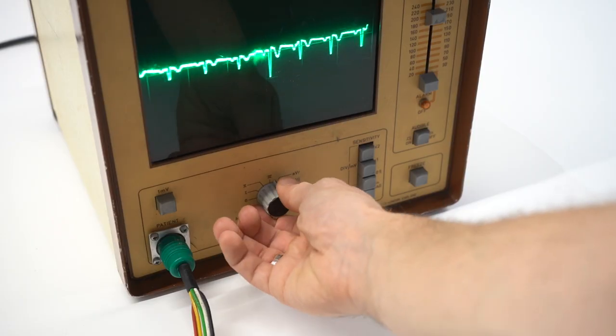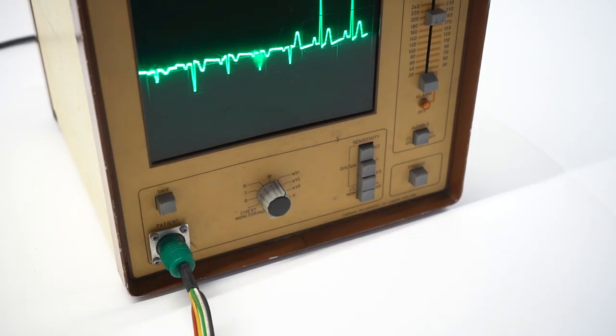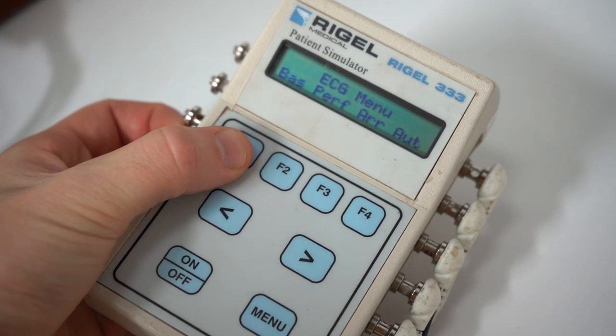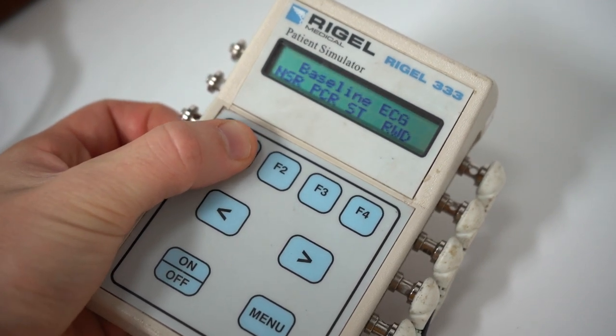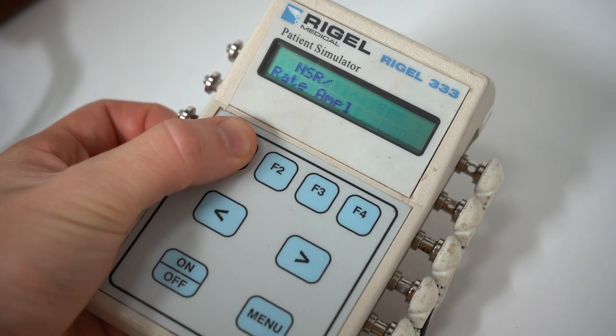Make sure this dial is set to this position for the classic heart rate pattern on the display. To change the qualities of the ECG, press the F1 button until you reach this menu.